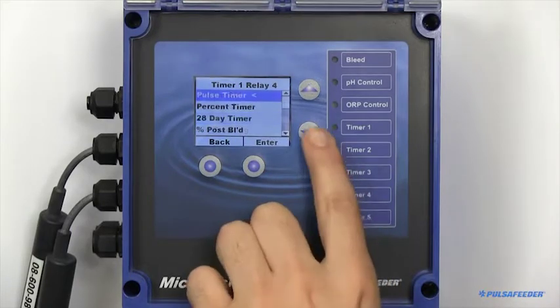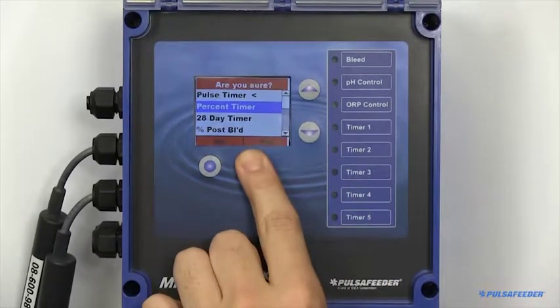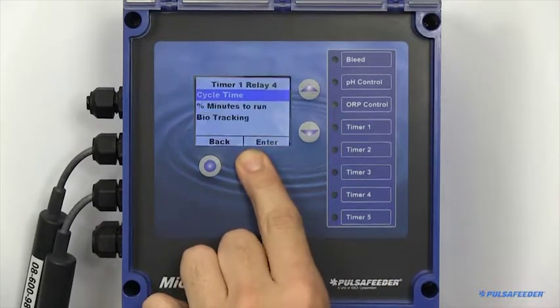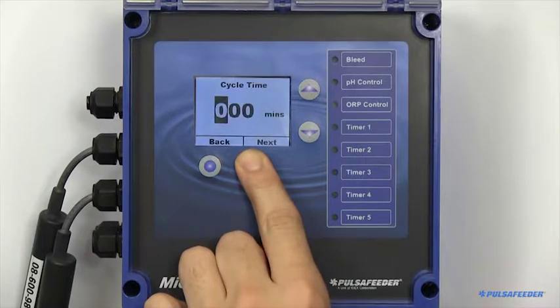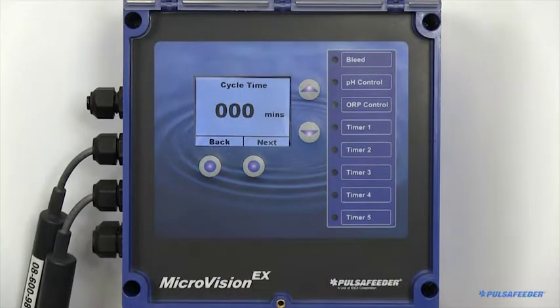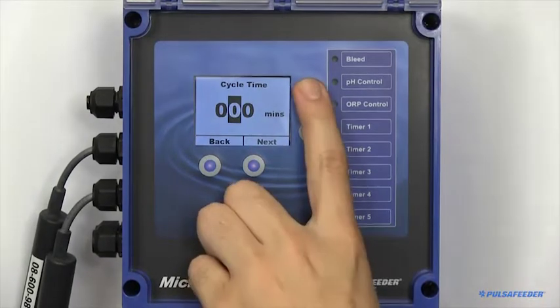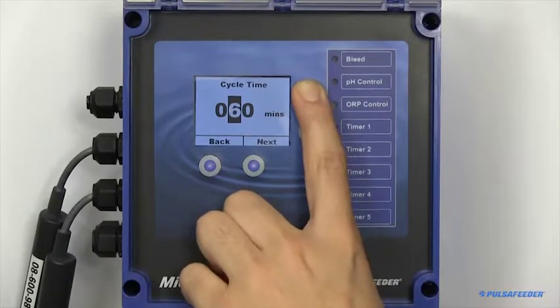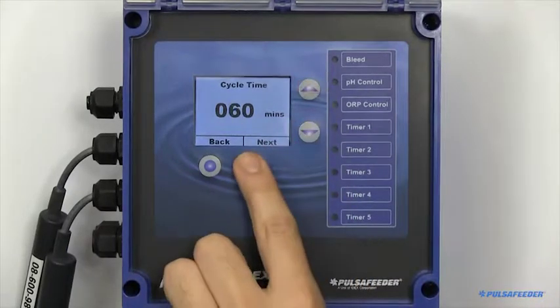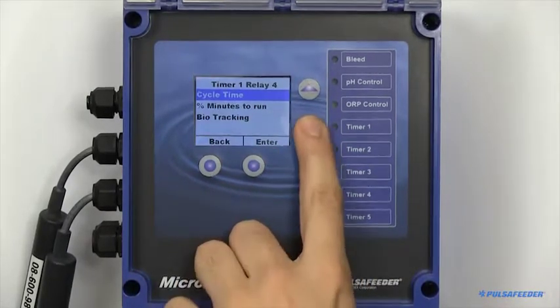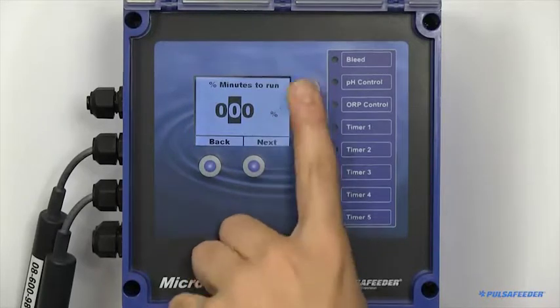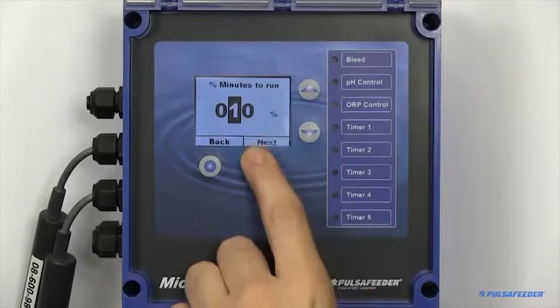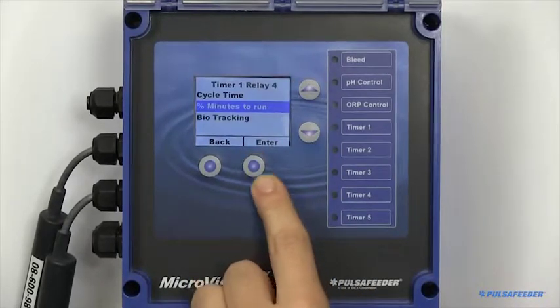There are two parameters when setting up a percent timer. You will need to set your cycle time, and your percentage of minutes you would like the timer to run. For example, 10% of 60 minutes would be 6 minutes of feed time every 60 minutes.